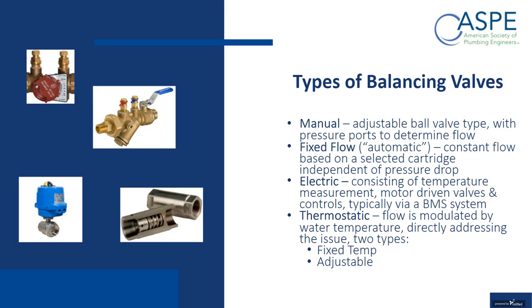There are several types of balancing valves on the market. Manual, which I'm sure a majority of you, if not all of you, have been exposed to and are probably still using, is more of a ball valve type of valve with pressure ports on it, which are used to determine the flow. The next one is fixed flow, which has several names: fixed flow, pressure independent, automatic. Basically, it's a valve where you place a cartridge of a given flow rate, and regardless of the pressure drop, that valve will always produce the same flow rate through that branch or riser.